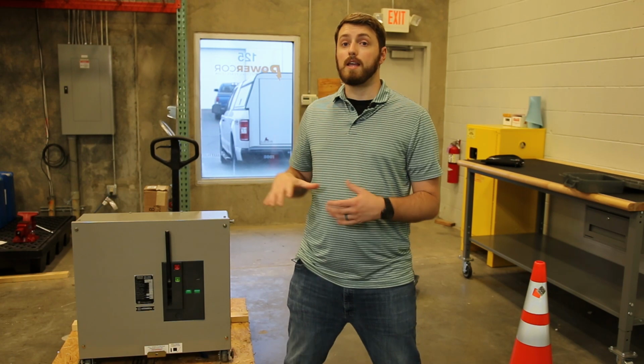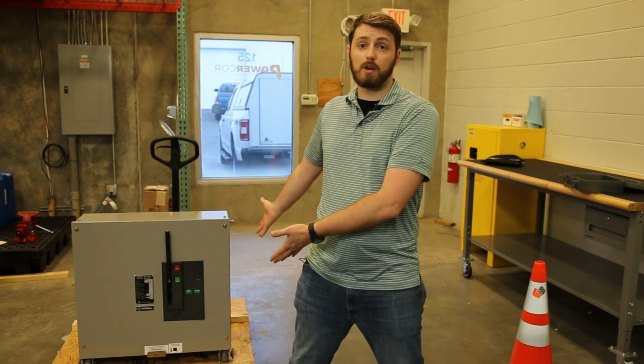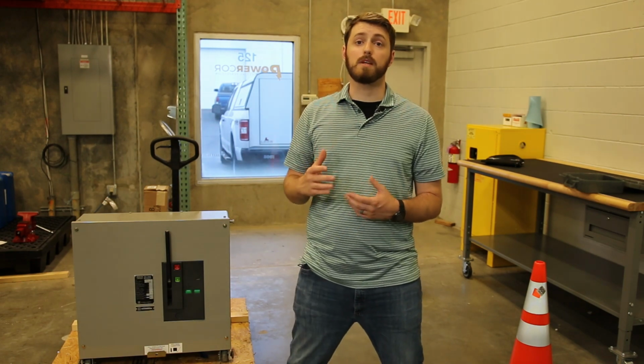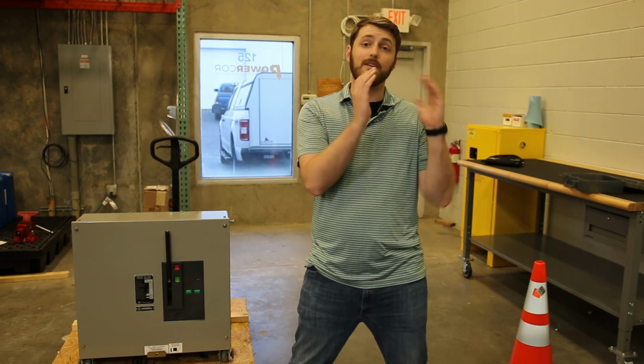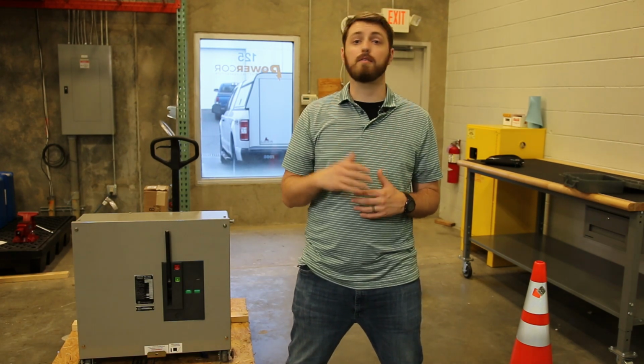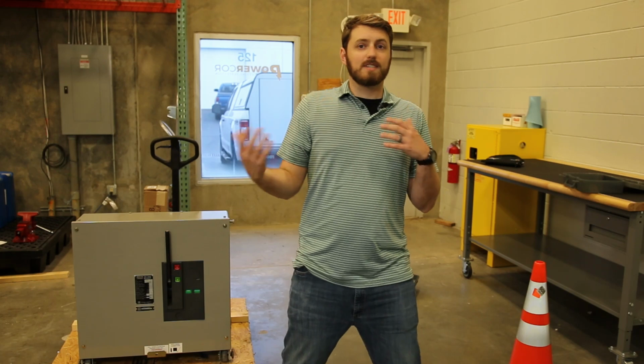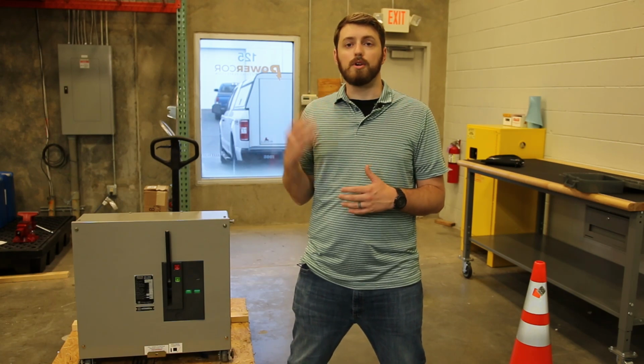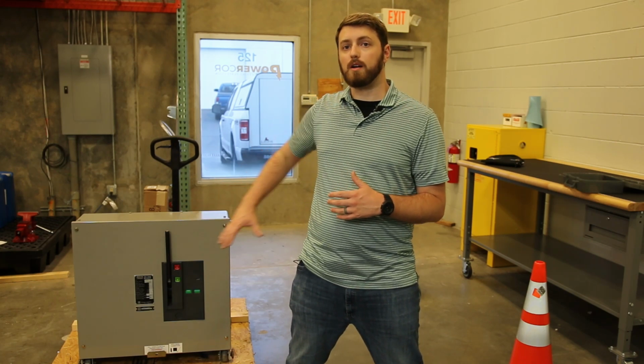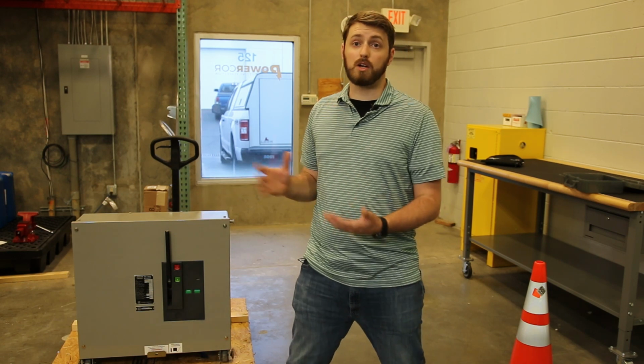We're going to make sure if it's in the cell, here I've got one on a pallet, but if it's in the cell, we have to make sure that it operates from every trip device. So every relay, every SCADA, DCS input that can open and close this breaker. We need to verify that those work with the breaker racked into the test position. Clean and lubricate. I'll show you where the lubrication points are.